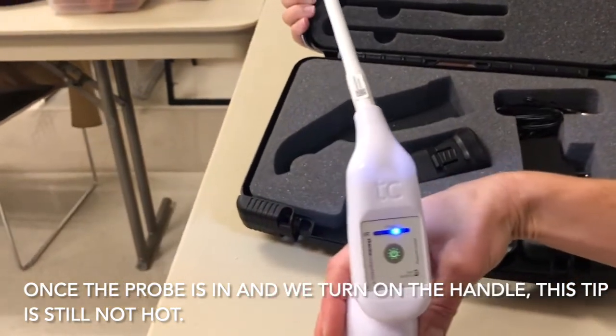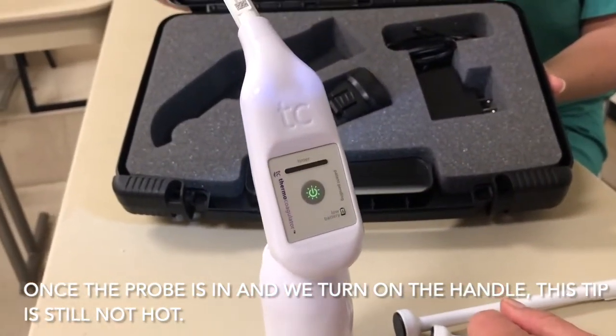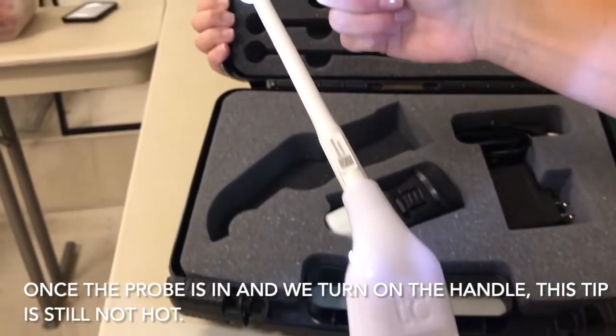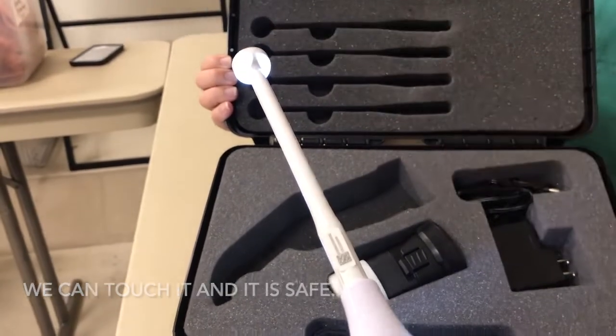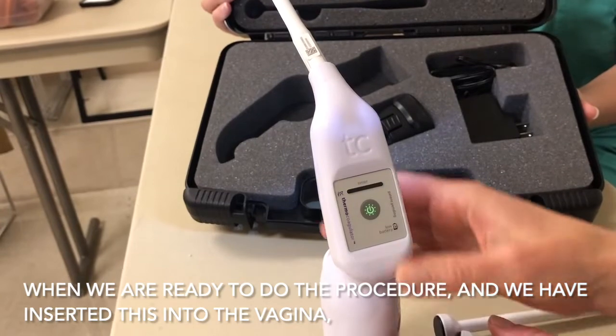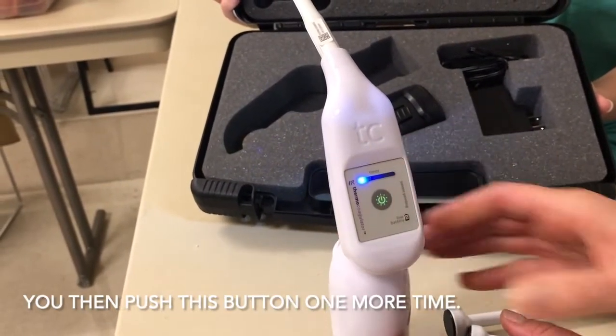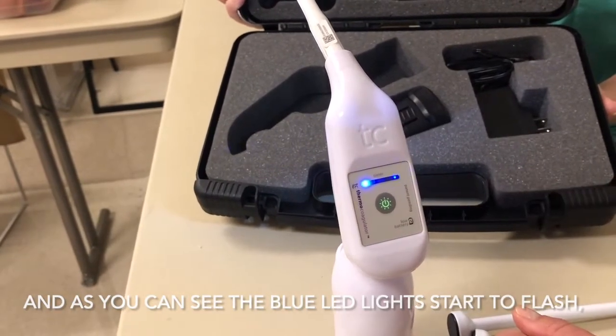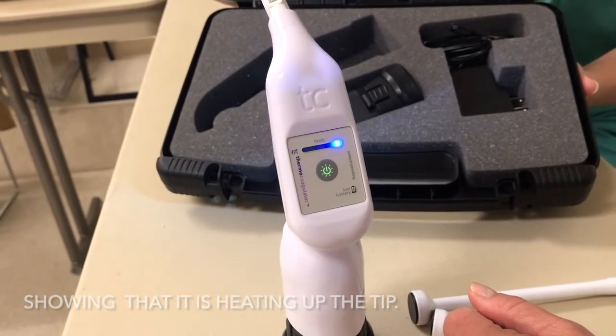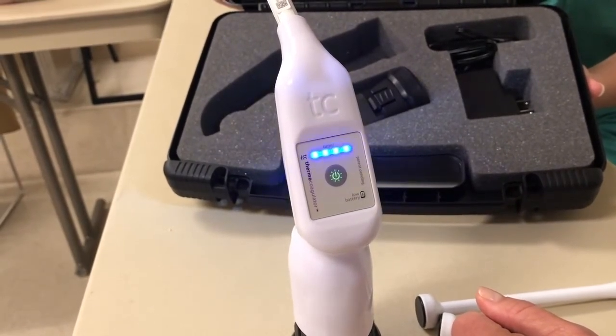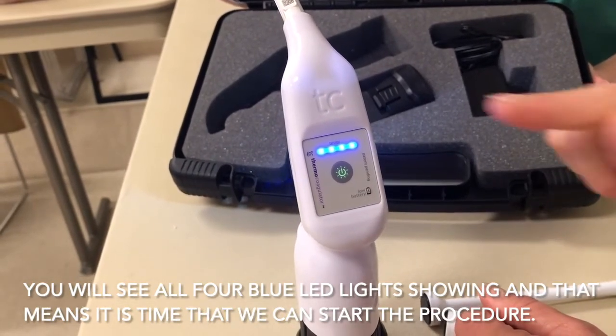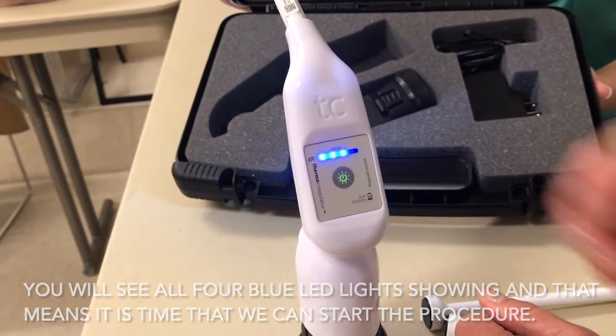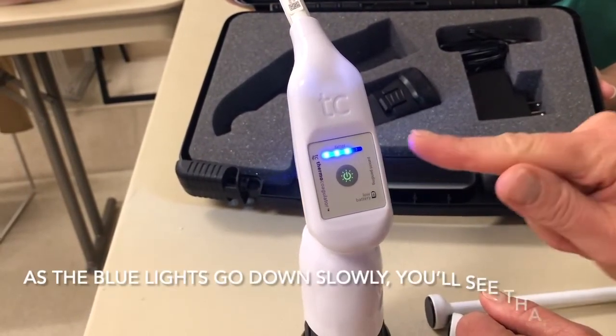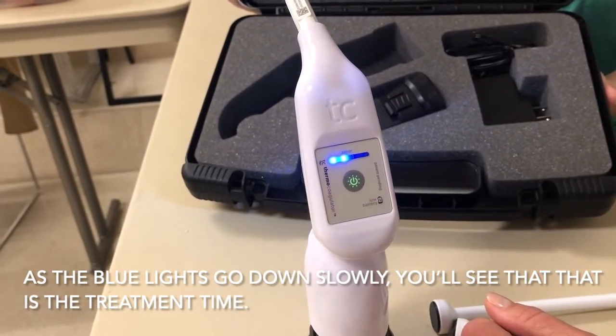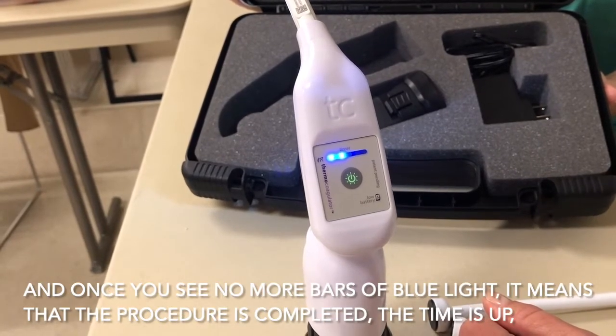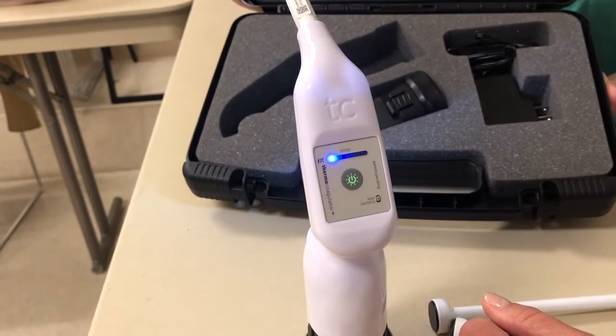Once the probe is in and we turn on the handle, this tip is still not hot. We can touch it and it is safe. When we're ready to do the procedure and we have inserted this into the vagina, you then push this button one more time, and as you can see, the LED lights start to go, showing that it is heating up the tip. Once the tip is completely heated, you will see all 4 lights showing, and that means it is time that we can start the procedure. Now it's heated. As it goes down slowly, you'll see that that's the treatment time. And once you see no bars, it means that the procedure is completed, which is typically around 20 seconds for that treatment time.